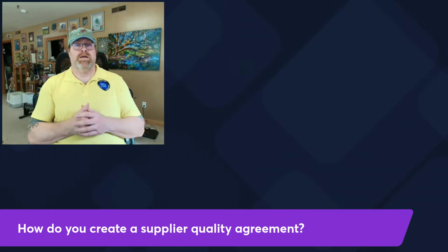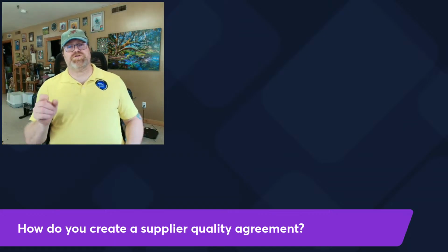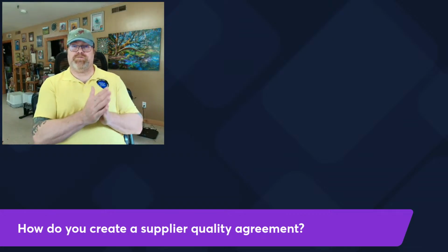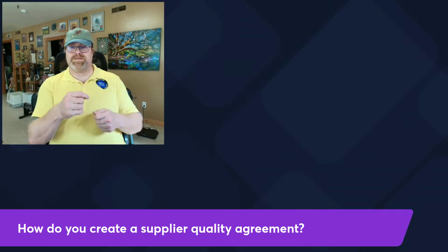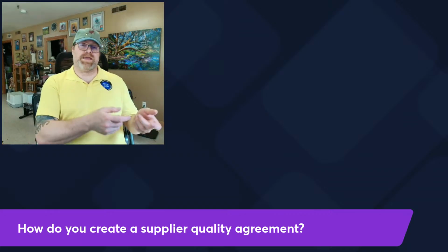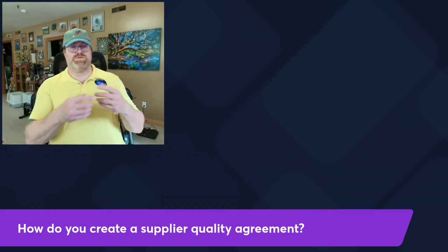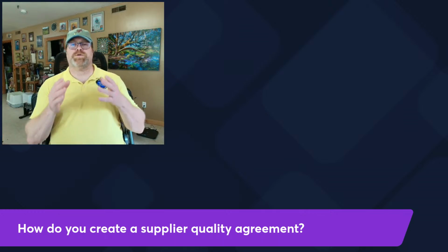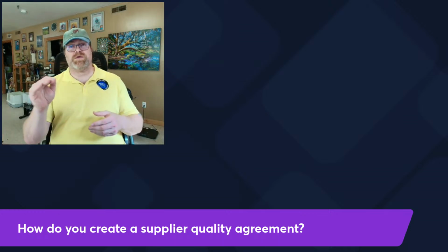You're only going to see that if you're doing a trend. So we ask people, when they get these flexible film Tyvek pouches, to do peel tests. You do them at the beginning of the lot, you do them at the end of the lot, you take samples, you take retains, whatever your policy, but you're supposed to be trending that so you can see when there's a shift.